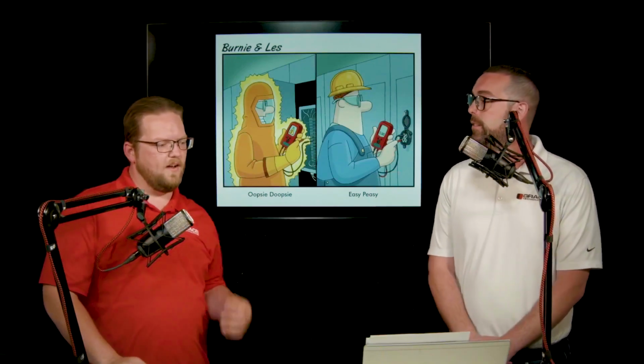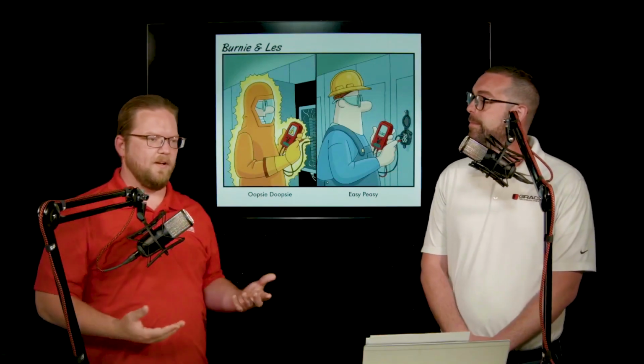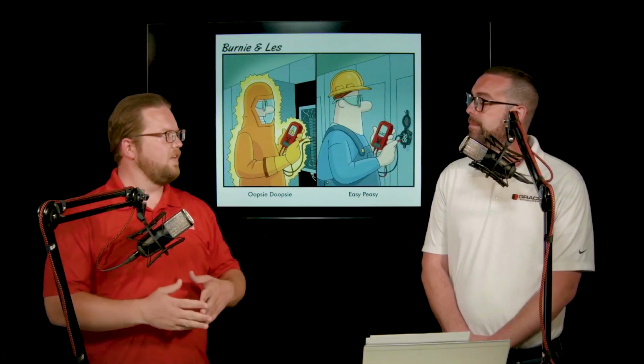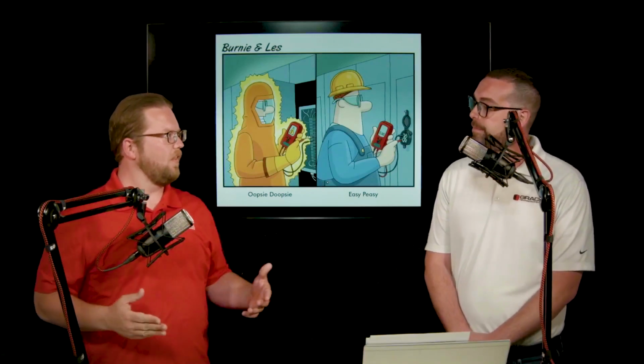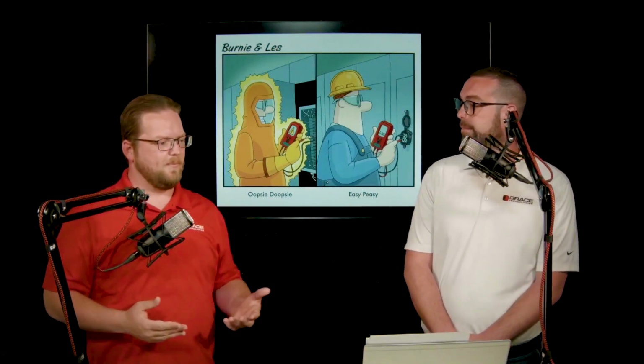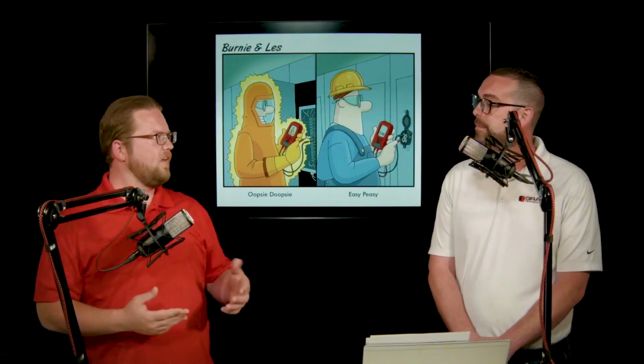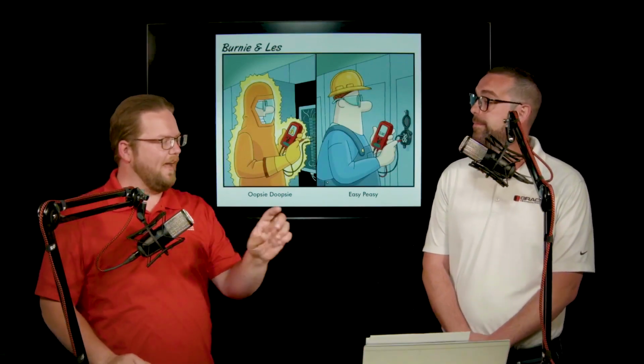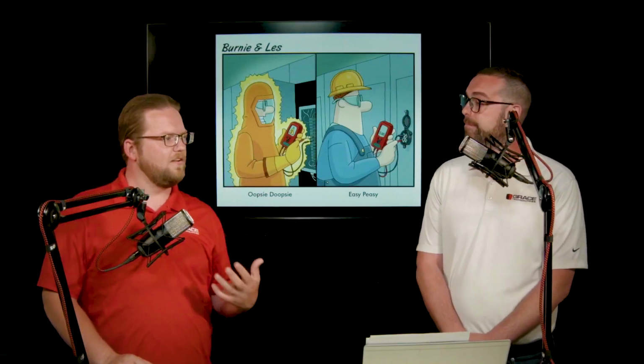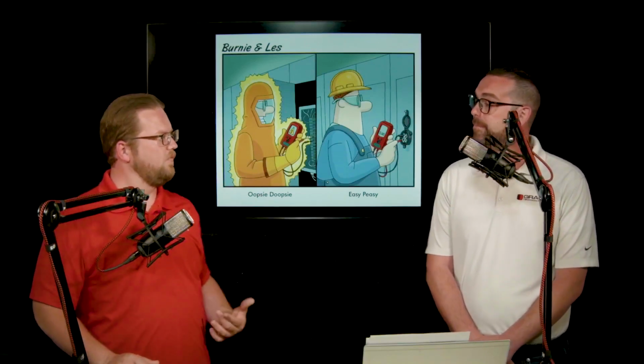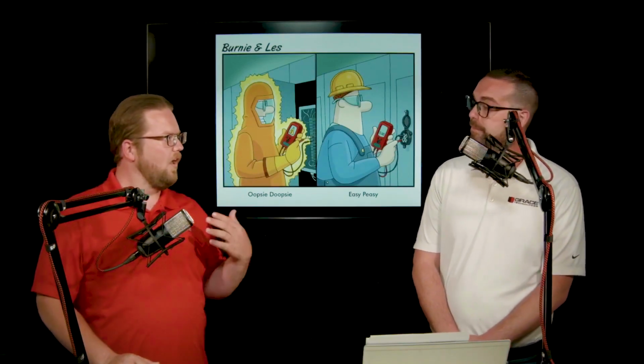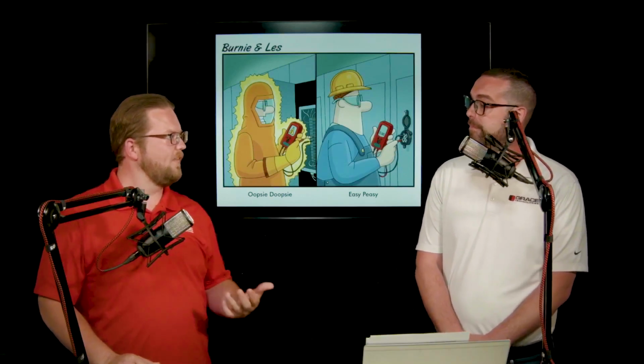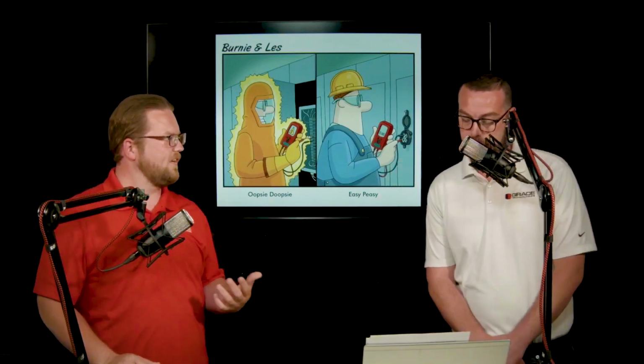One of the other questions on that topic was determining the equipment needed to perform a lockout tagout safely, or to perform absence of voltage testing. One way is that if you have the arc flash rate and calorie rating on your equipment, you can determine what level of PPE is required. But is there another way if you don't have that utility short circuit data? What options do customers have?